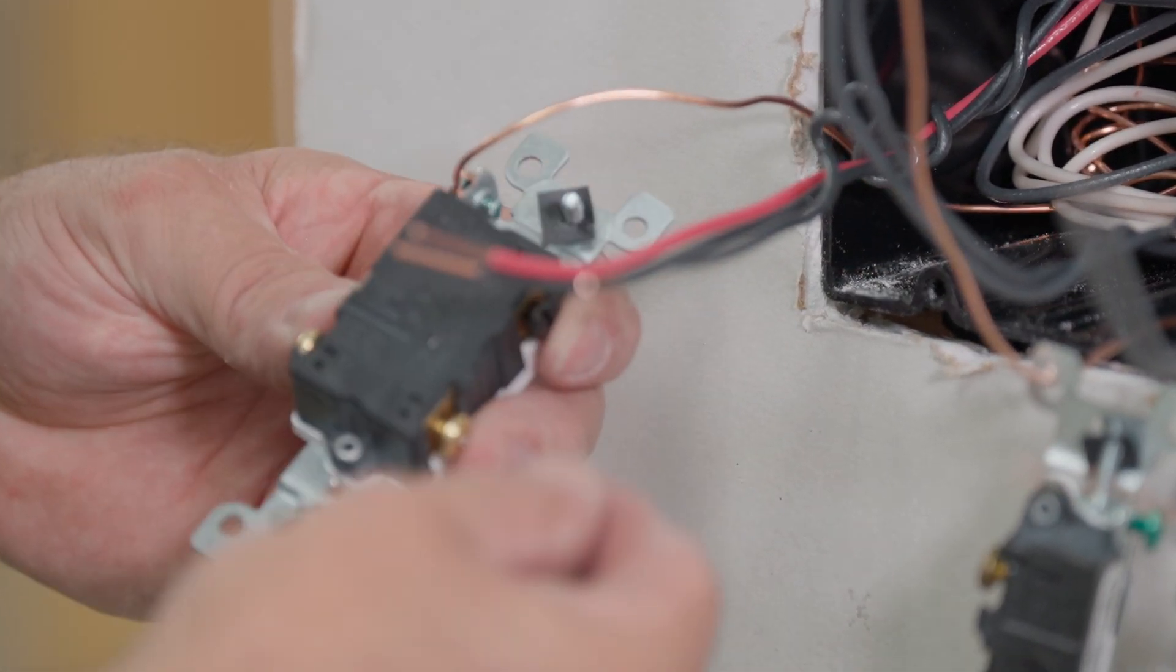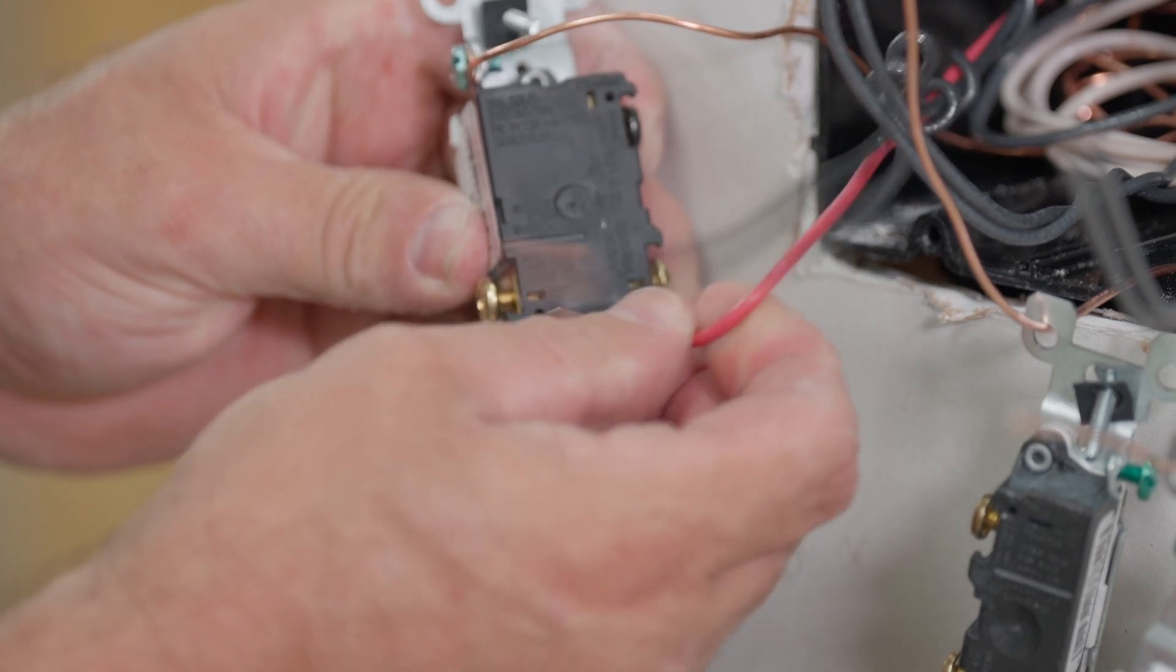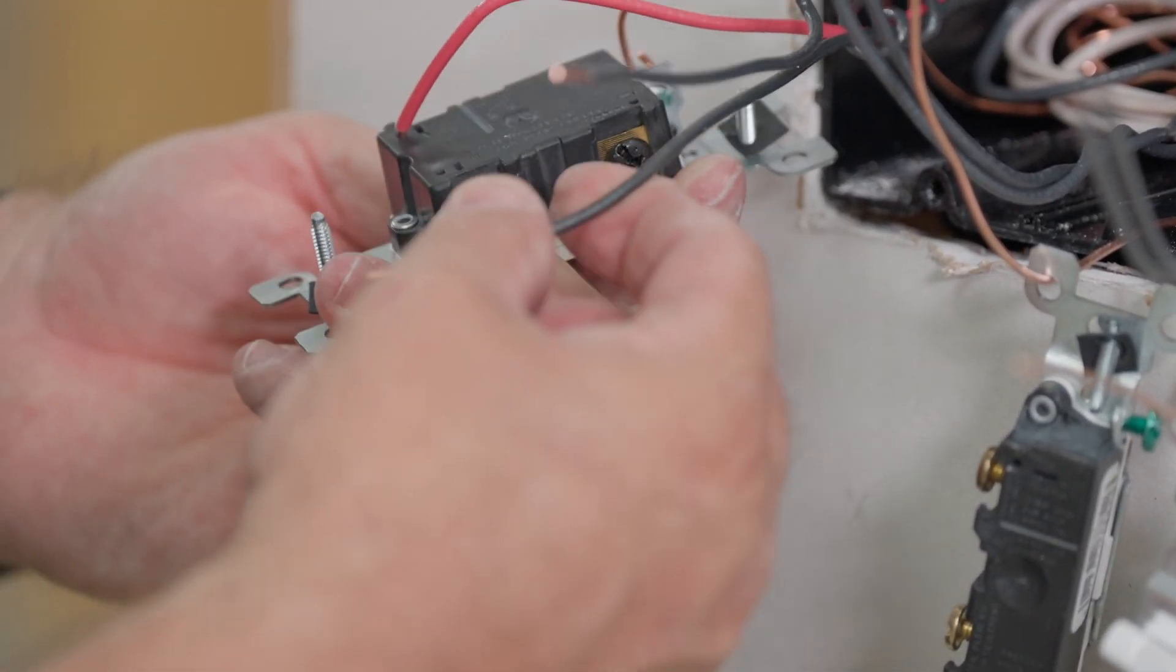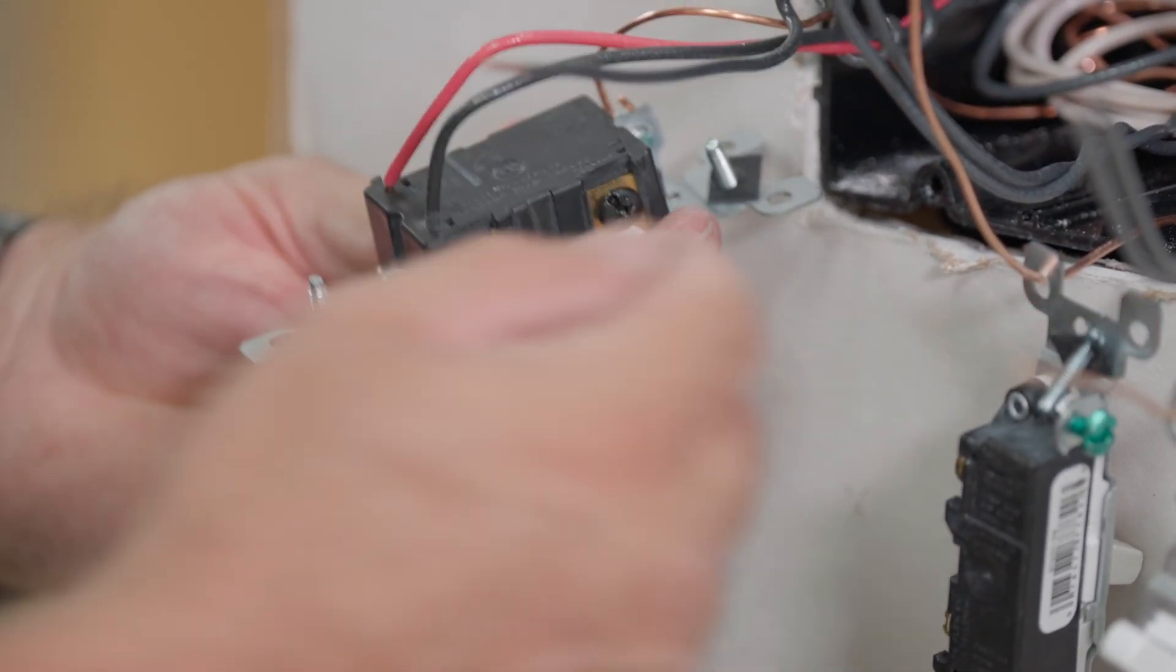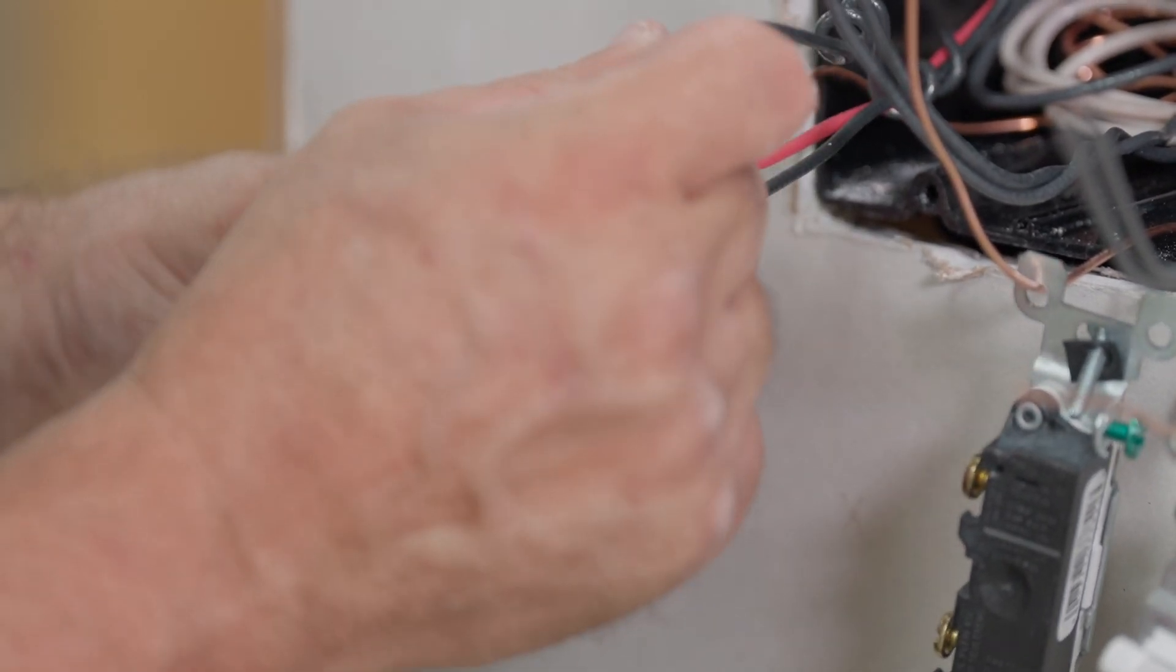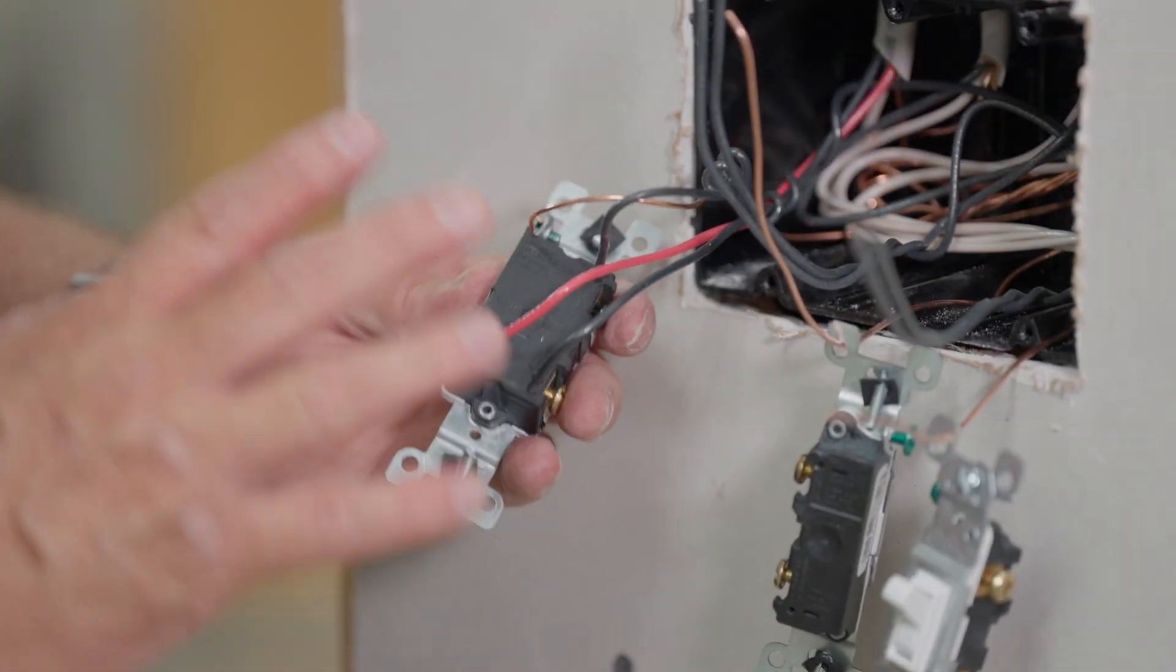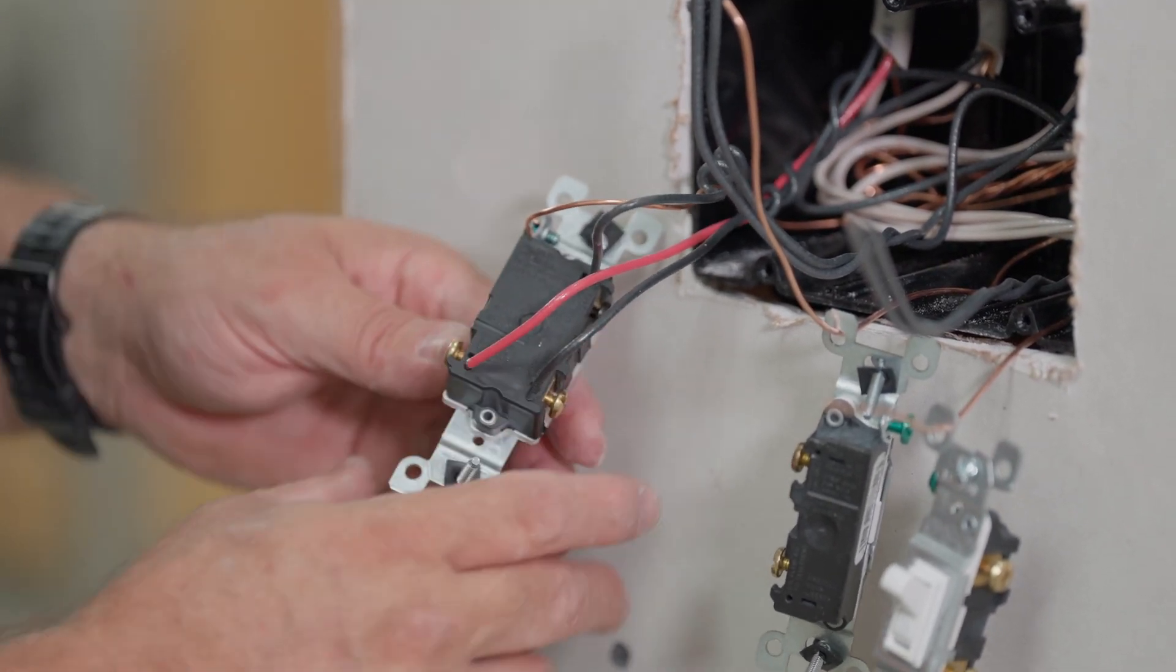So what we'll do first is here's the terminal here. We'll put one of the travelers and push it in the back just like that. And then here is the other traveler. It's brass. We'll push it right in the back. And then here's the black common. Make sure you get this right. This is the biggest mistake people can make when wiring a three-way switch. You got to make sure the common is in the right place and the traveler is in the right place.